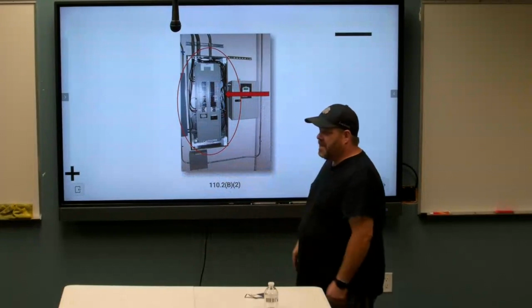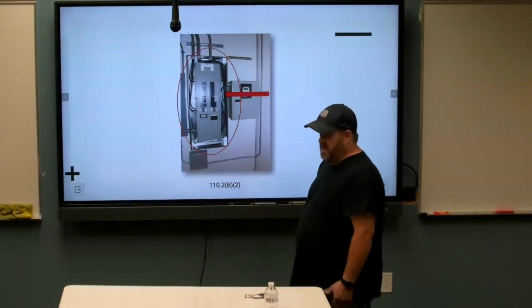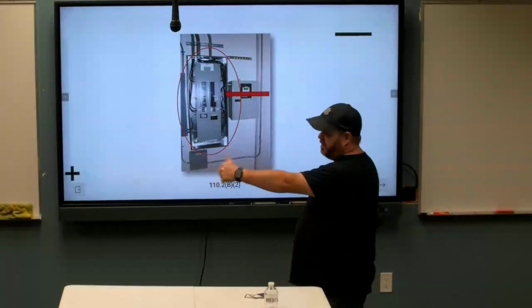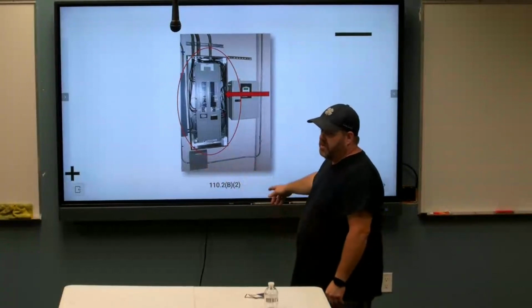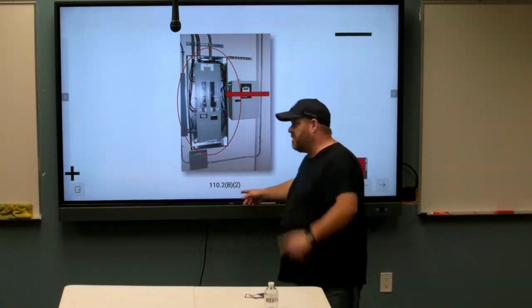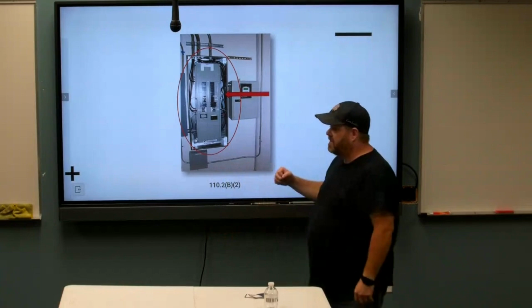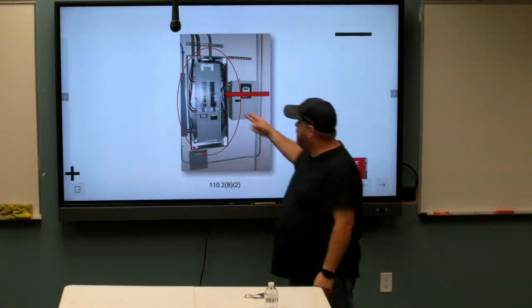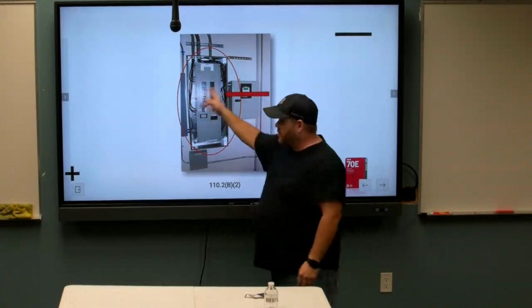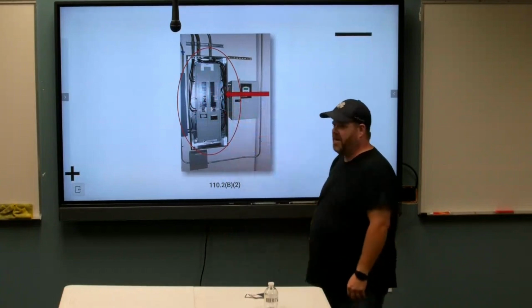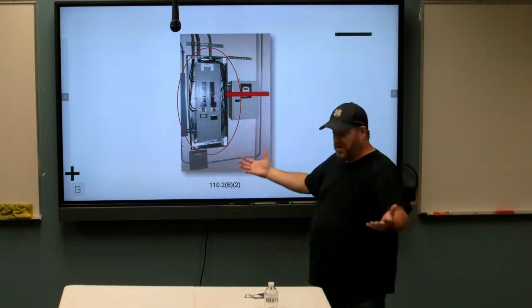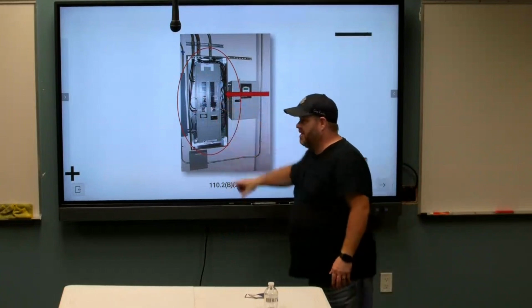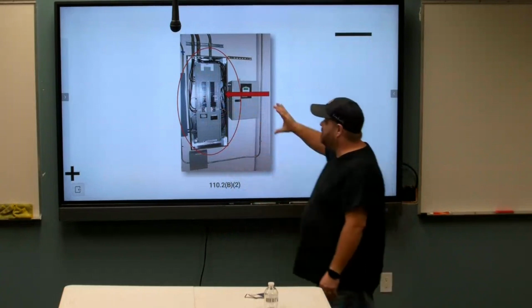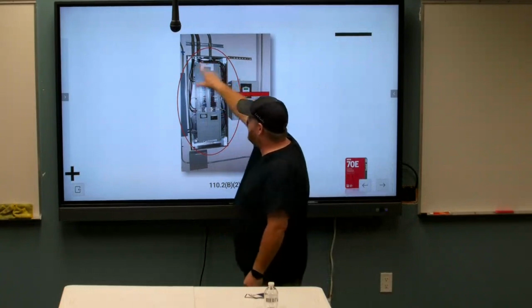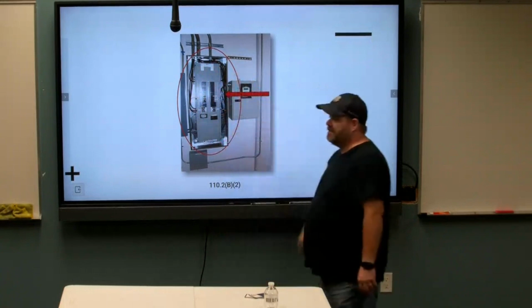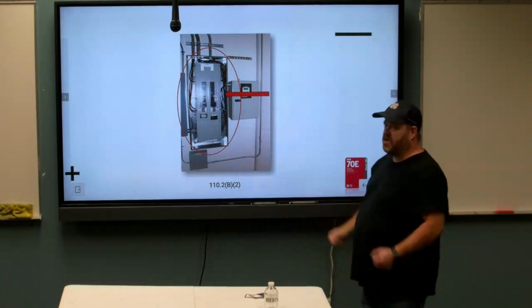there underneath the panel. And I asked the foreman, is this live? And he said, yeah. That's okay though. I got the dead front on. And I said, well, okay. What if the T-grid contractor goes to pick up a pile of that seismic wire? Do you think that seismic wire could contact these energized conductors or circuit parts behind the dead front? He goes, oh yeah. You left it exposed. You left a hazard sitting there, and somebody could have been killed. So even when you take the cover off, but you leave the dead front on, if that panel is energized, you're exposed. Does that make sense? Things can go wrong.